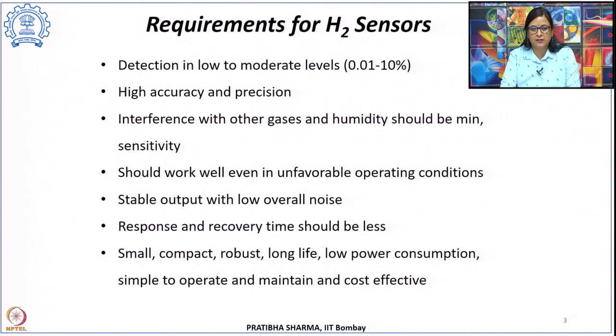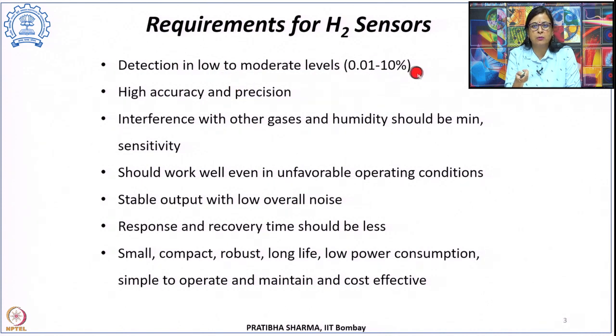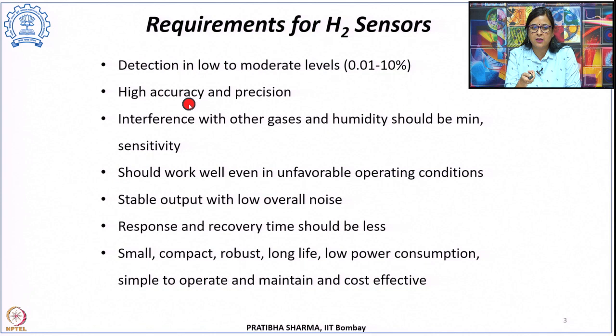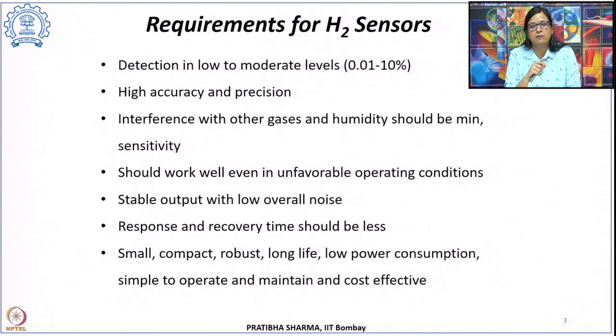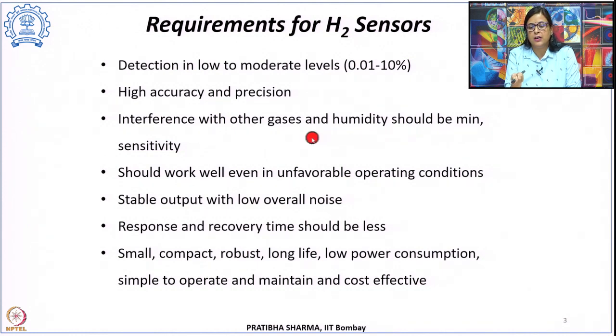When it comes to hydrogen sensors, there are several requirements these sensors should meet. They should detect hydrogen across a wide concentration range — from low to moderate to high, say 0.01% to 10%, or even up to 100%. Accuracy and precision should be high, and there should be no interference with other gases, so selectivity and sensitivity towards hydrogen should be very high. There should also be no cross-sensitivity with humidity.